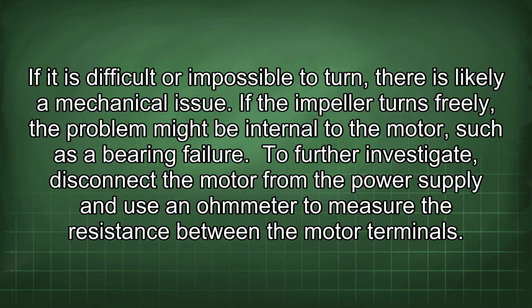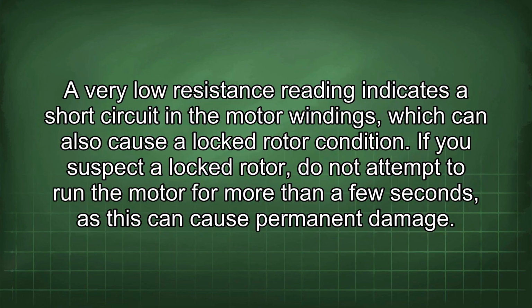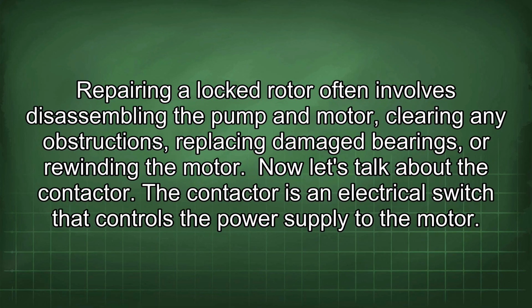To further investigate, disconnect the motor from the power supply and use an ohmmeter to measure the resistance between the motor terminals. A very low resistance reading indicates a short circuit in the motor windings, which can also cause a locked rotor condition. If you suspect a locked rotor, do not attempt to run the motor for more than a few seconds, as this can cause permanent damage. Repairing a locked rotor often involves disassembling the pump and motor, clearing any obstructions, replacing damaged bearings, or rewinding the motor. Now let's talk about the contactor.